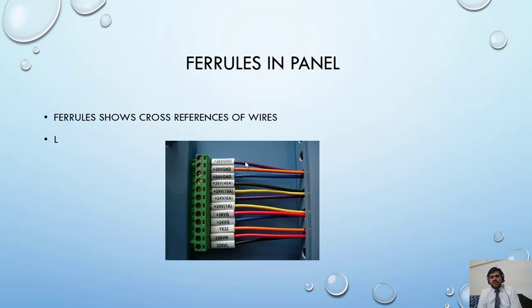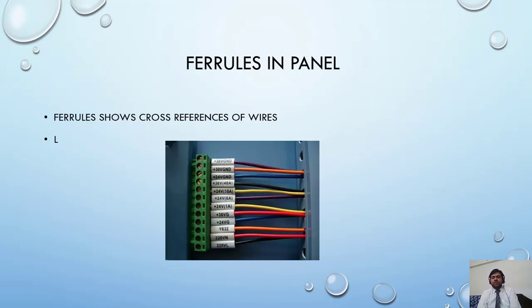At the end of the sheet you will find a termination schedule or terminal assignment. In this termination schedule or terminal assignment, the terminals are mentioned, and against each terminal the source, from and to, and which wire is connected to and from the terminal is shown very clearly. This is how ferrules work and what you should know about them.